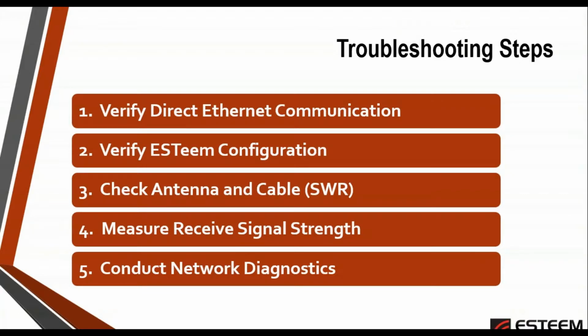So what we've done is put this into 5 very simple troubleshooting steps. The first thing we do is verify whether we have Ethernet communication between the computer we're troubleshooting on and the radio itself. Something may have happened to the Ethernet port, or it may be set to a different IP address, something configured that way. This may be as easy as opening the Discover utility, pushing the Discover Radios button, and seeing if the radio replies back.